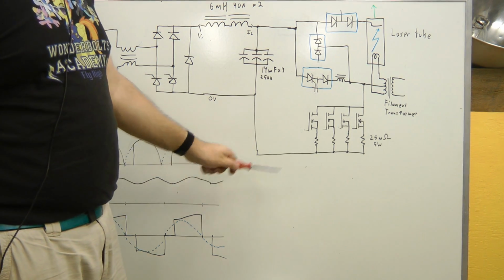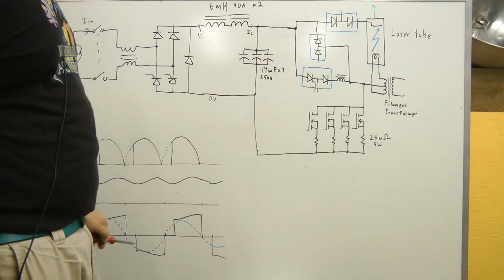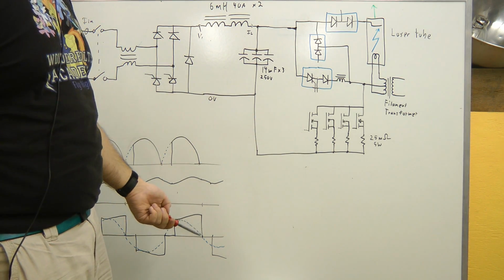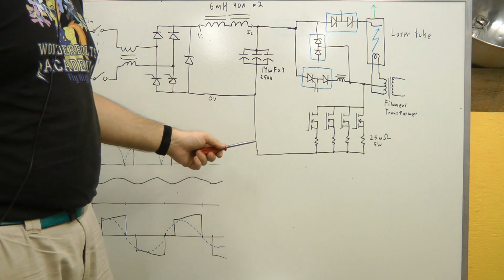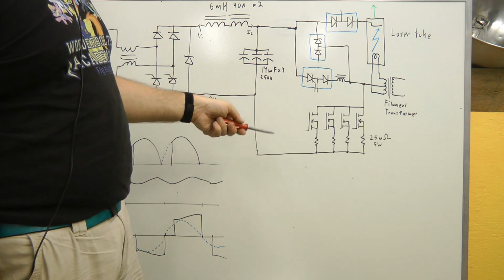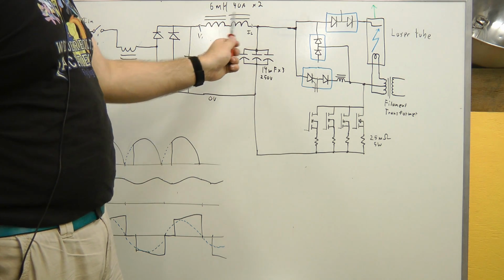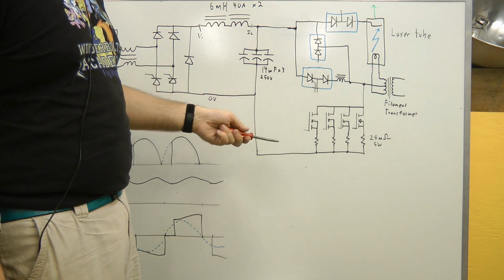I think the reason they're using this linear power supply design rather than a switching supply is this has to be able to produce precise narrow pulse widths. And with a switching supply, you'd have to wait, for example, for the current in an inductor to ramp up or down, and they don't want that here.